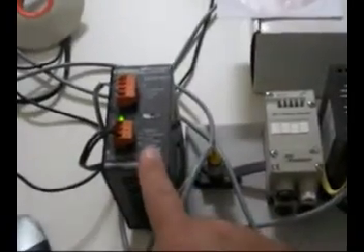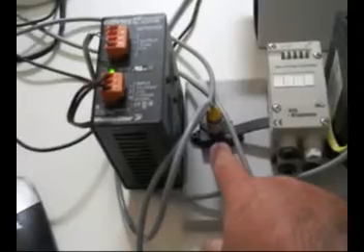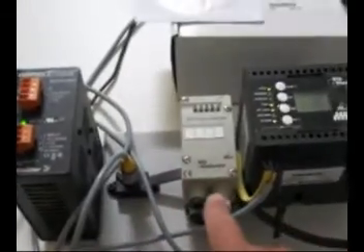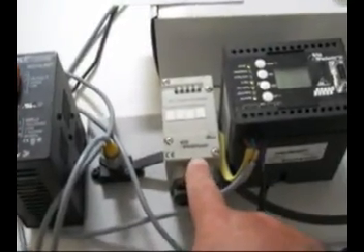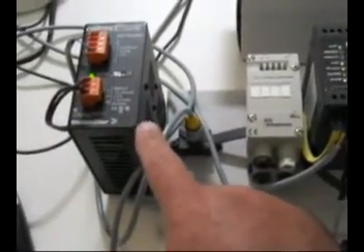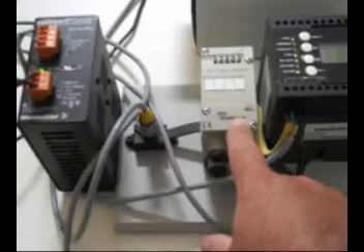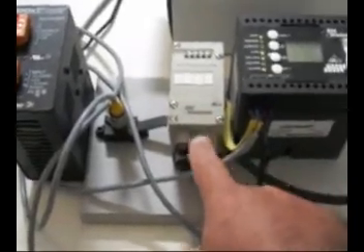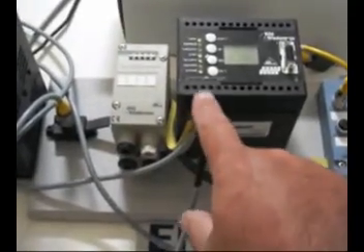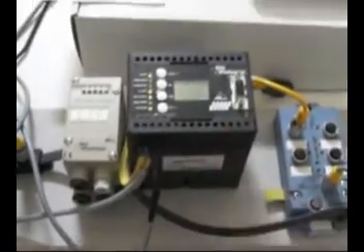Then our little demo system here, we've got a standard power supply connected right here, 24-volt DC power supply. We've got that wired into this connector here, which then goes into the Bihl Wiedemann power extender or conditioner here. That takes this standard power supply and converts it to an ASI power supply. It decouples that supply for us. And then from there we've got that coming into our power network here on our ASI master.